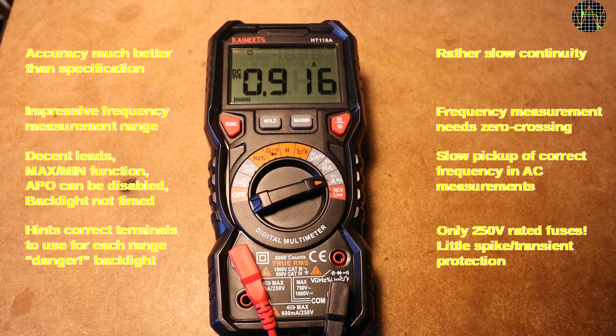when leaving the leads in the amp setting and trying to measure voltage. Finally, although the meter claims 1000 volts Cat3 and 600 volts Cat4, the fuses are only rated for 250 volts and there's very little other input protection, making it vulnerable to transients and spikes. I do not recommend using this meter for anything else than normal electronic workbench stuff and maybe routine household mains measurements like at sockets on light fixtures, but not for measuring inside power consumer units, switchboards or large electric motors.